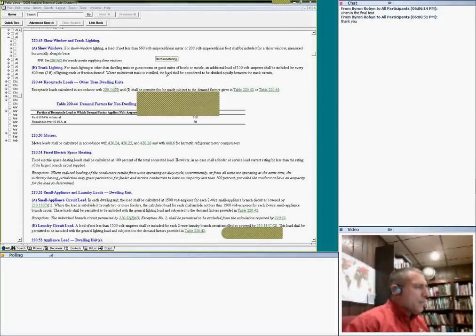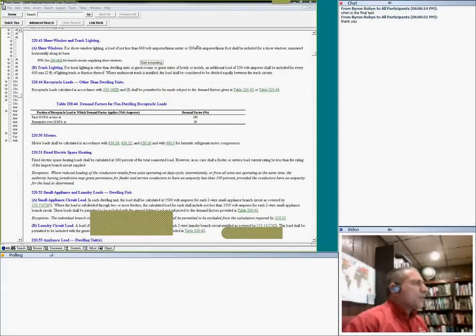Let me just go here for show windows. 200 volt-amps per linear foot. So how many feet? 100 feet multiplied by 250. That's your demand continuous load. If you have track light, can you see that? Track light, 150 volt-amps for every 2 feet of track light. So do your math on that one.